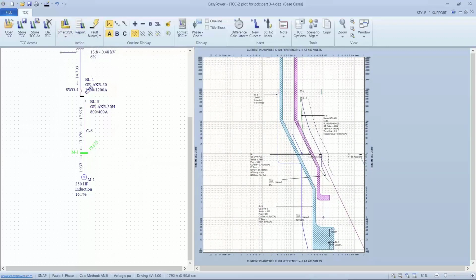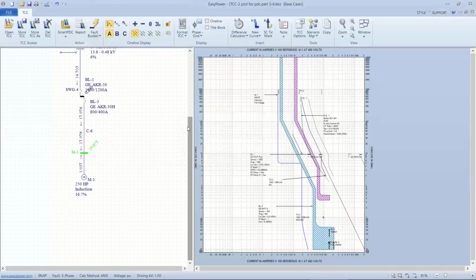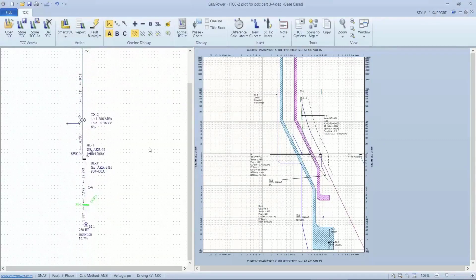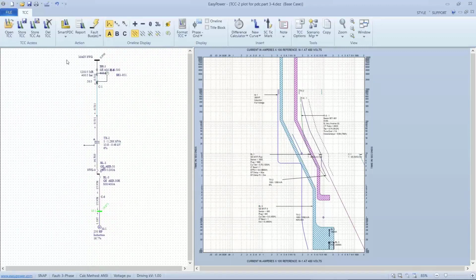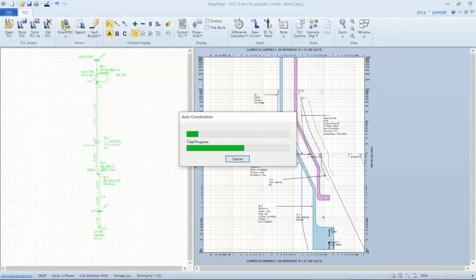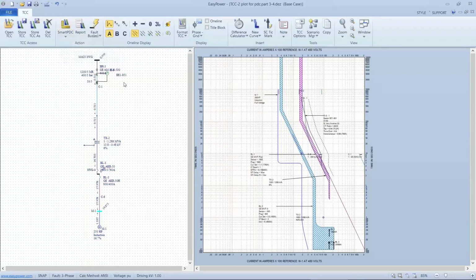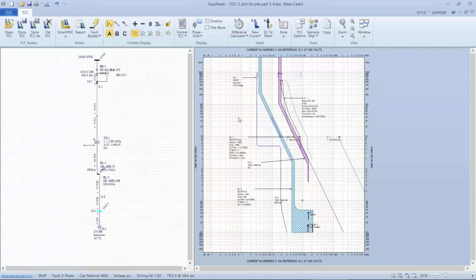So we have coordination. We have some miscoordination on the relay. And it's telling me that it didn't like the downstream route. And so it pretty much ended up with what I did, without a recommendation on coordination here. So in this case, I think I'm a little bit better off not following the smart PDC, because I like having the protection against the overload relay.